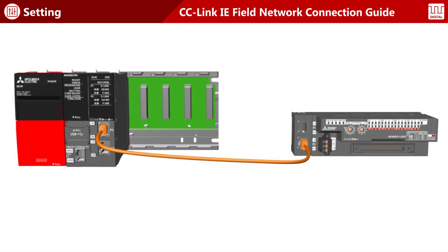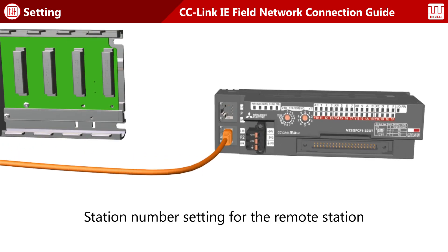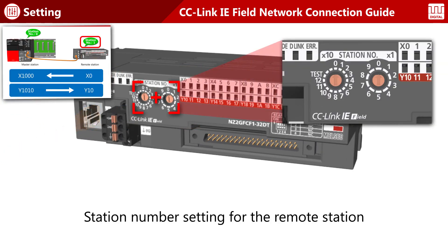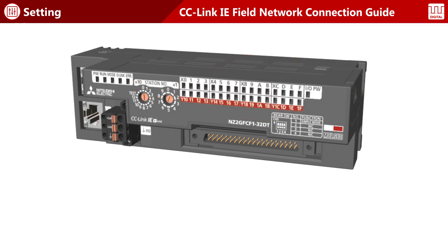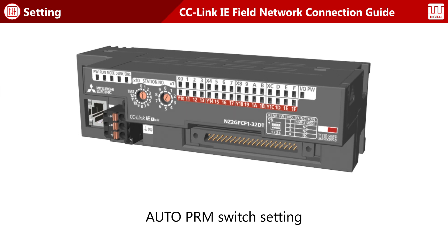The procedure for hardware settings is described. Station numbers for remote stations are set using the switch on the front of the module. The remote station is station number one, so set the station number to one. Now, enable the function that simplifies the setting procedure for typical operations.